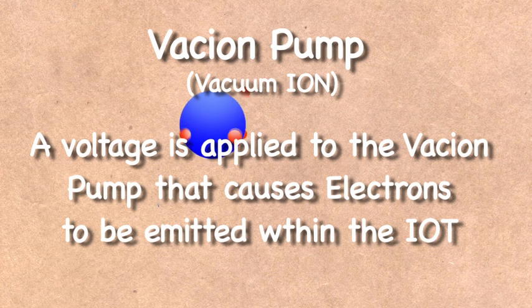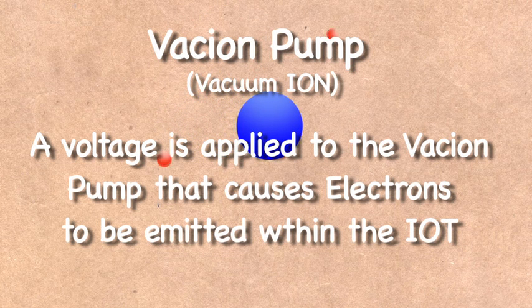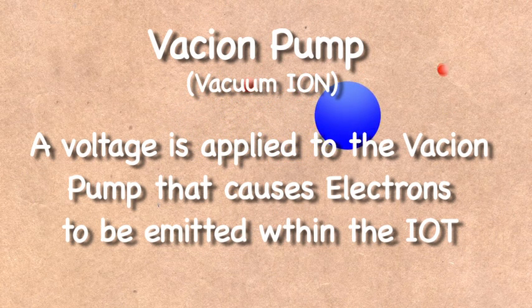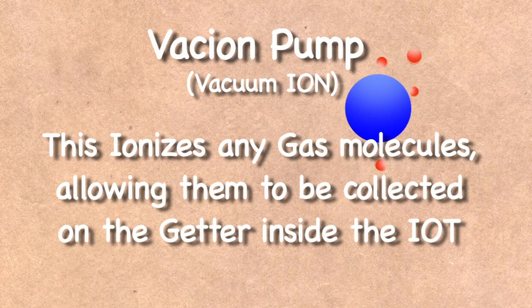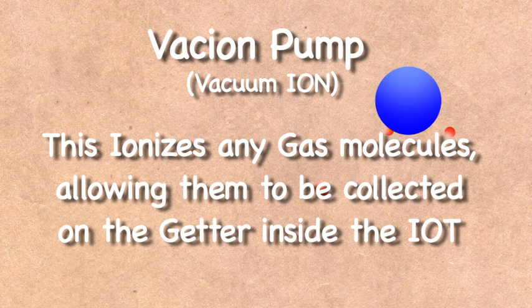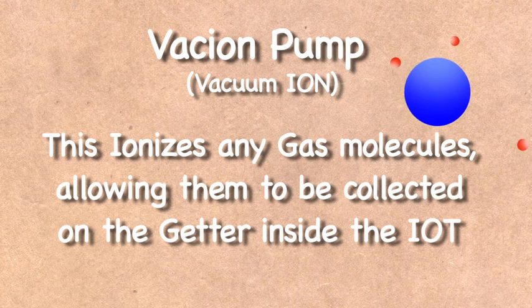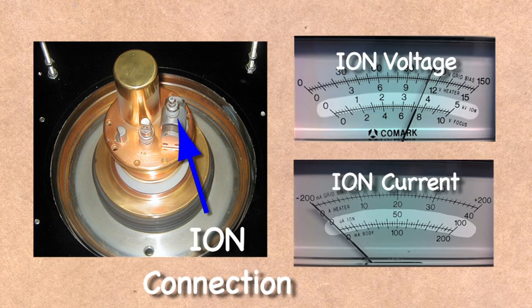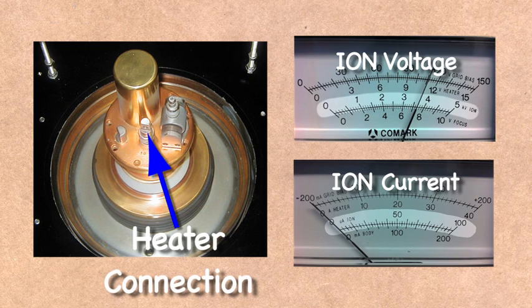Another aspect of IOTs is maintaining their internal vacuum and preventing the buildup of any gases within. To do this, an ion pump is used. A voltage is applied to the ion pump that ionizes any gas molecules which are then attracted to a getter within the tube. A typical ion voltage is 3.7 kilovolts with zero current draw. Any current drawn by the ion pump indicates the presence of gas within the tube. This can lead to arcing.